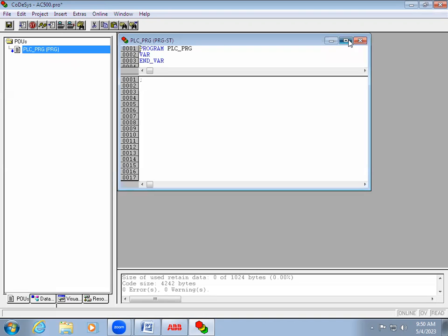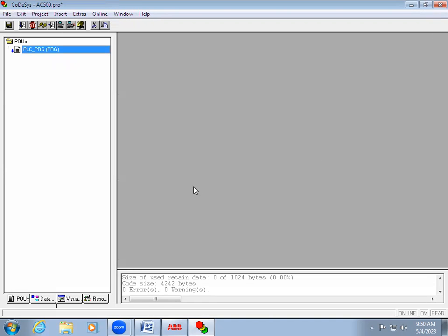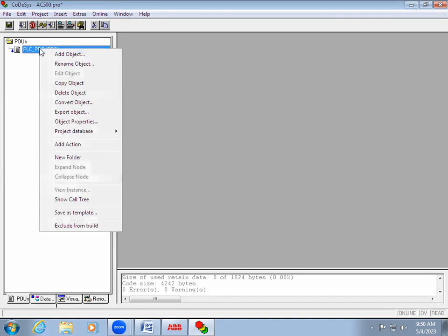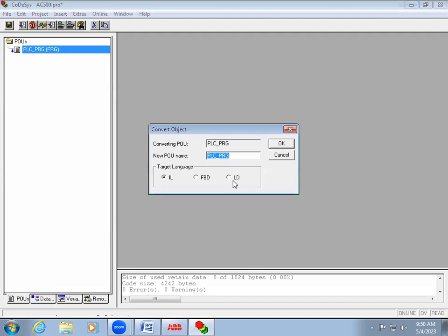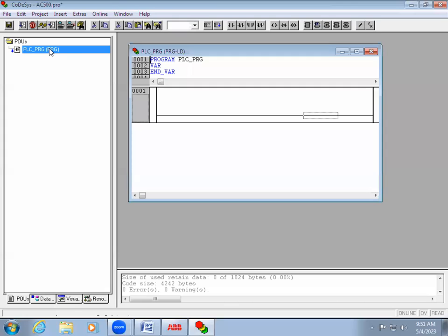Without the main program we can't use it — just like in Omron we have a default Section 1. In ABB they give PLC_PRG and the default language is ST (Structured Text). When I double-click it opens in ST language. Since we need Ladder Diagram, I'll right-click PLC_PRG, then choose Convert Object, select LD, and click OK. Now the main page has been changed to Ladder Diagram language.